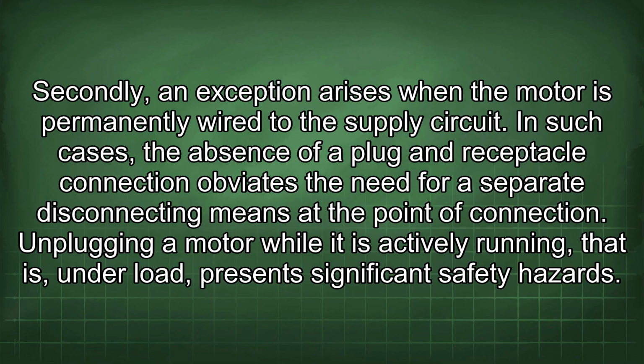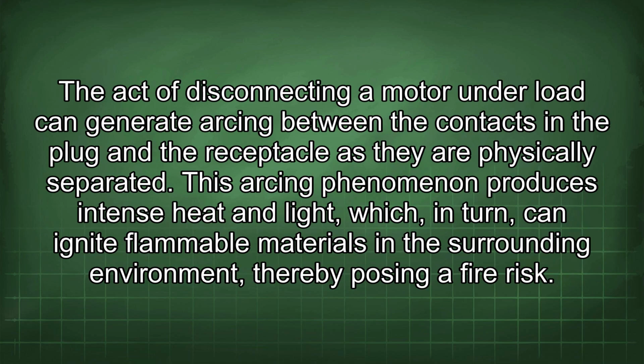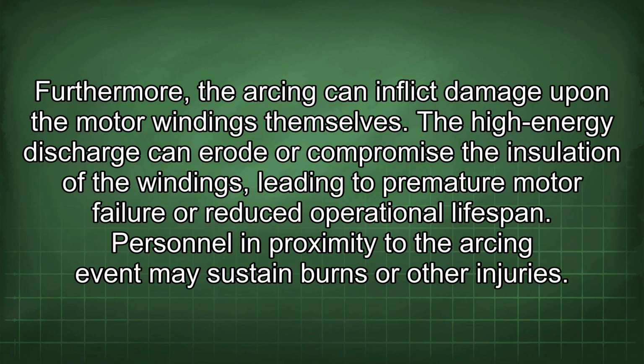Unplugging a motor while it is actively running, that is, under load, presents significant safety hazards. The act of disconnecting a motor under load can generate arcing between the contacts in the plug and the receptacle as they are physically separated. This arcing phenomenon produces intense heat and light, which, in turn, can ignite flammable materials in the surrounding environment, thereby posing a fire risk. Furthermore, the arcing can inflict damage upon the motor windings themselves.